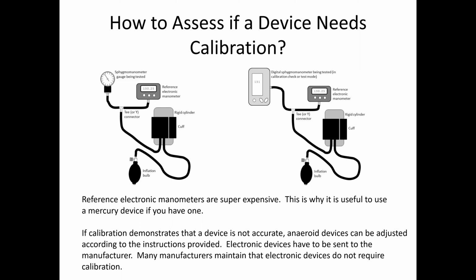You call out on the reference device that it's at 300, and then your partner can look and see what the actual device under test is at, and so on and so forth. You go down by 50 to 250, 200, et cetera. And by doing this, you will be able to tell whether it's within 3 millimeters. I should have put that on the slide, actually. It needs to be within 3 millimeters at each blood pressure point to be considered accurate. And if it isn't, then it's drifted, and especially the aneroids drift over time.